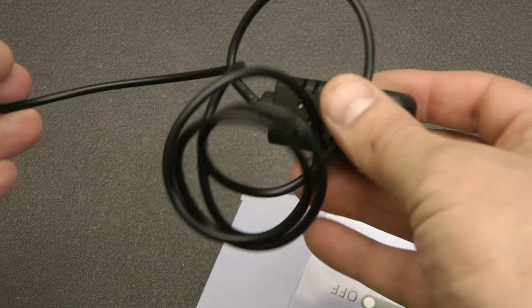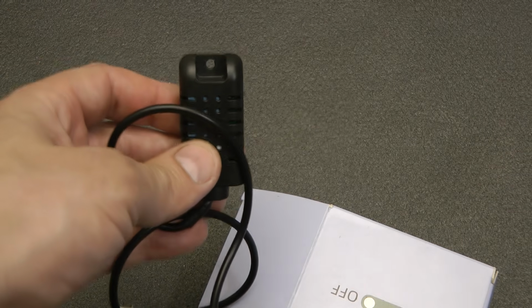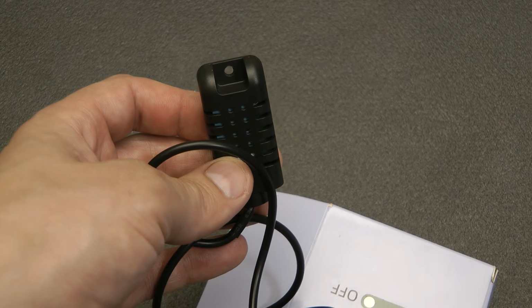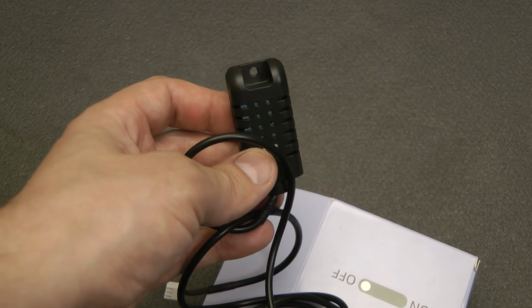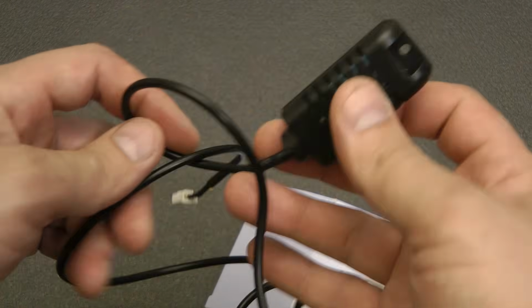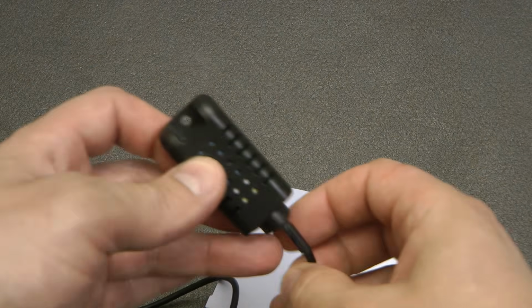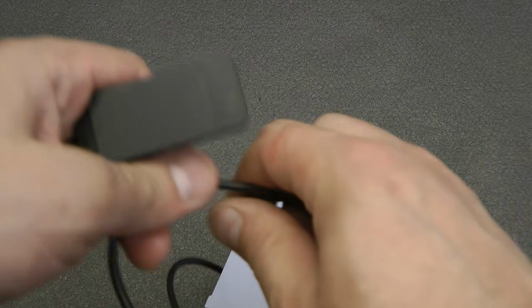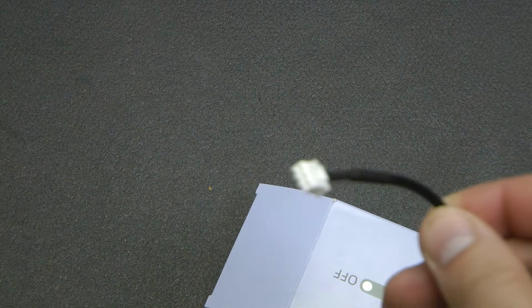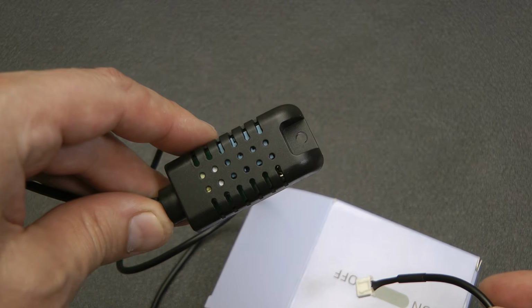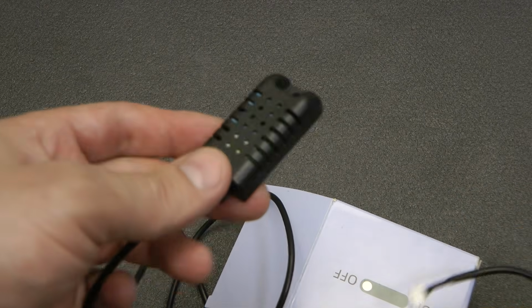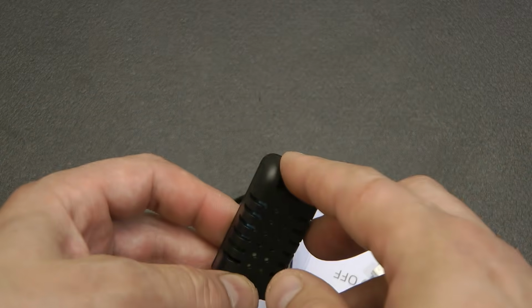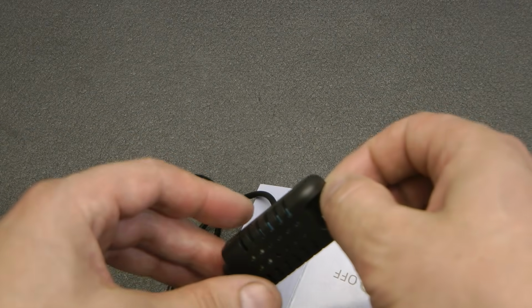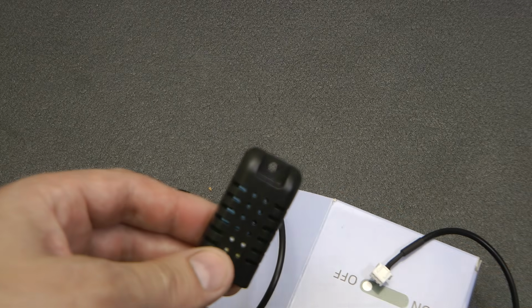When buying, you can choose the version with a regular temperature sensor. It is made in a sealed housing, so such a sensor can be used, for example, to measure the temperature of a liquid. In my case, this is an external temperature and humidity sensor. The cable length is a little over 1 meter. On one side, there is a 3-pin connector for connecting to the relay itself, and on the other side, the sensor body. Its back side is flat, so the sensor can be attached with double-sided tape, screwed in with a self-tapping screw, or simply hung in the right place, since the body has a special mounting hole for this.